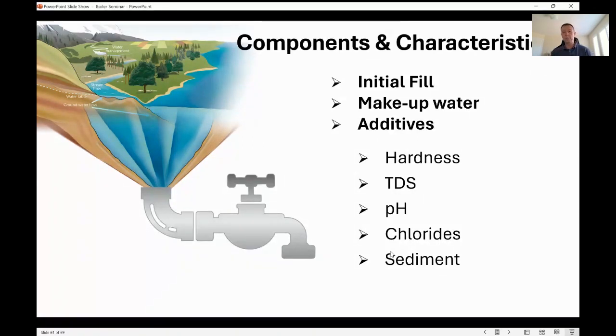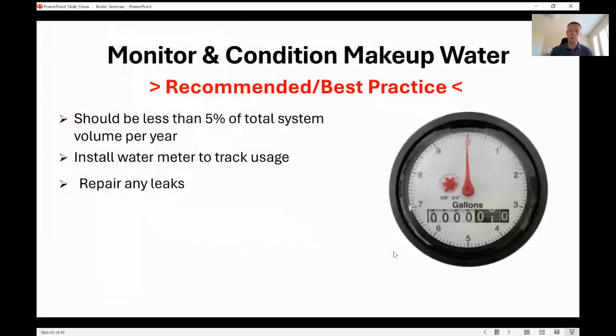I've seen where some people think it's a great idea to put their pool chemicals right next to the boiler. Well, that stuff gets in the air. If you're drawing combustion air from the room, that goes right in. As it gets in, it mixes with the condensate in the condensing boiler, and you can basically rot out that heat exchanger. And of course, sediment, that's going to build up in your boiler heat exchanger and once again cause a non-warrantable failure. I recommend monitoring your makeup water because sometimes there's leaks in the system.